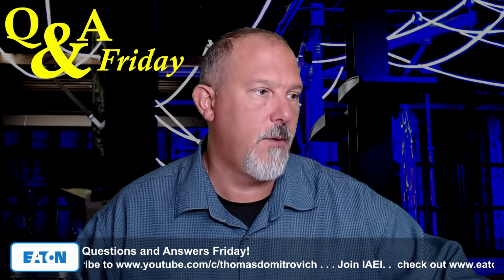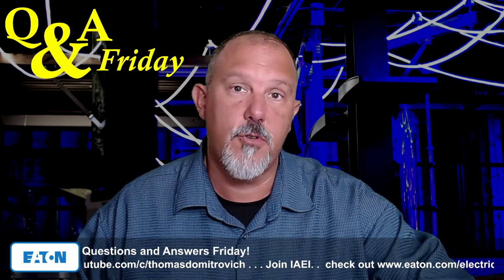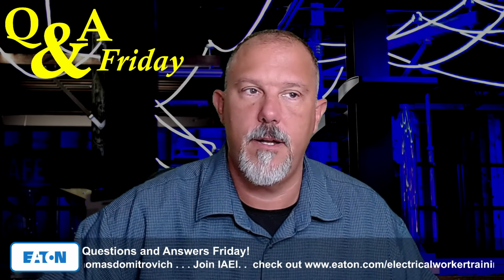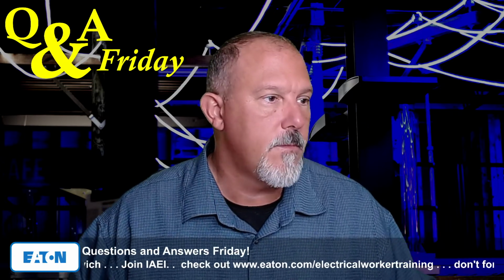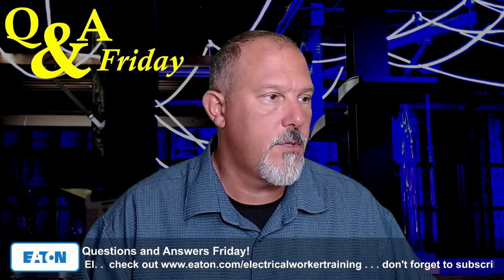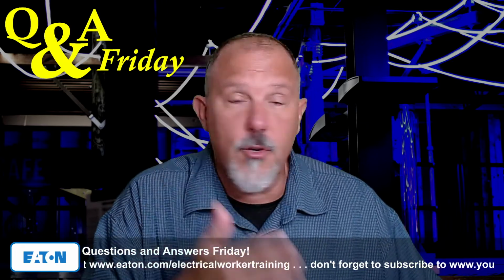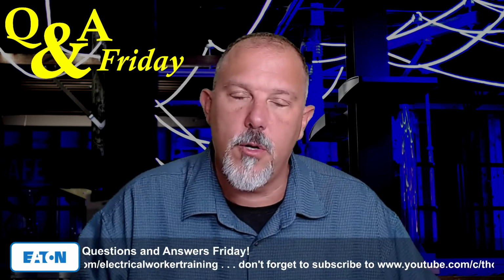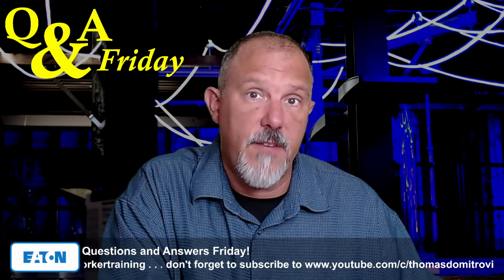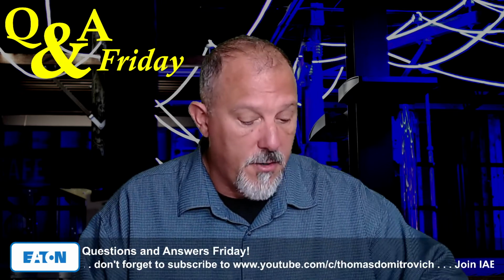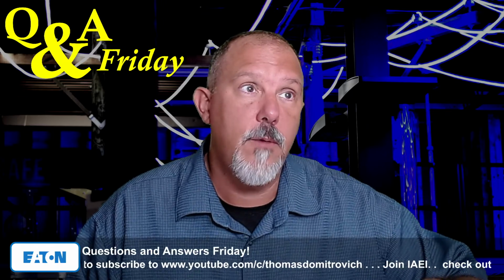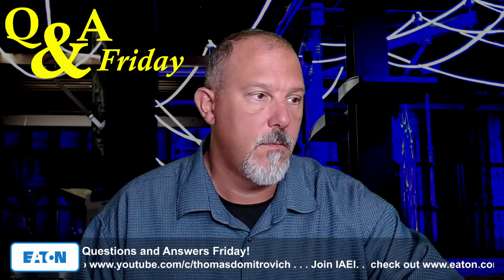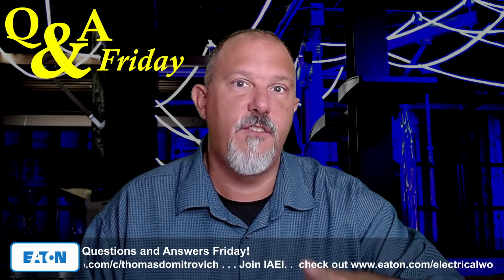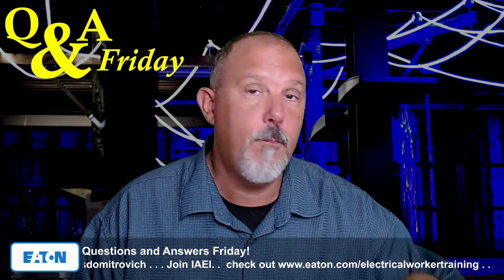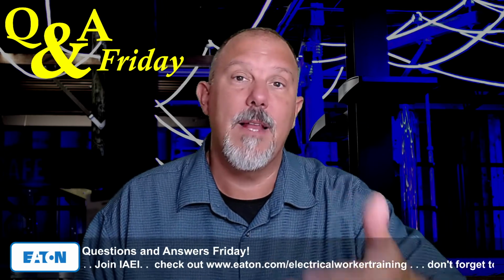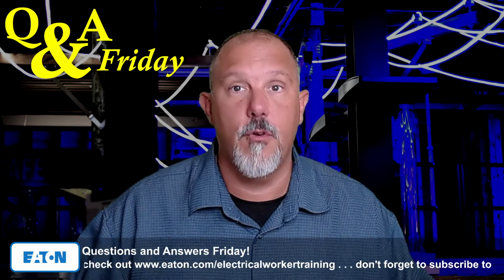So if the MID detects a fault current, it's not going to contribute. It's basically going to shut down if you have a fault, and you're not going to feed that fault. So regarding your comment that you might not have power for critical loads, if you're talking about Article 700 type loads, Article 700 has Part 3, sources of power. And I would question whether or not your source of power actually would suffice to meet the application, because of the reliability concerns that you would have for things like solar photovoltaic systems.